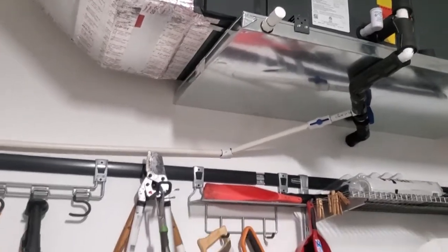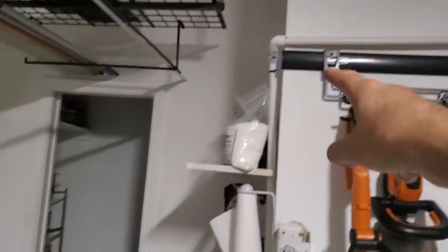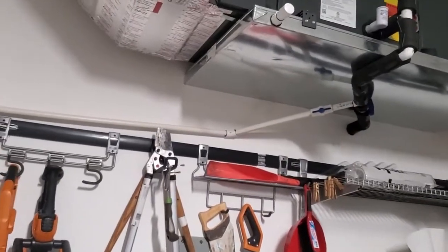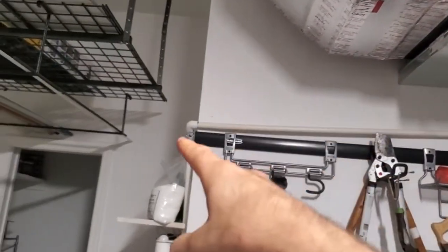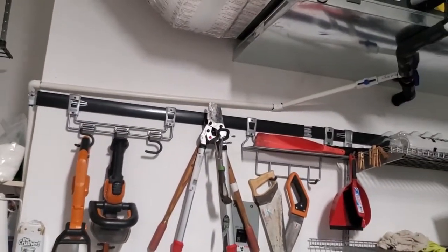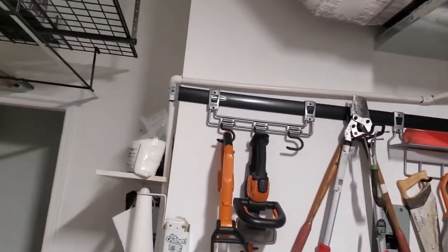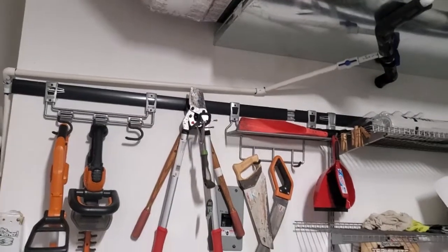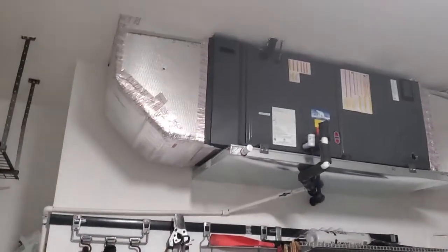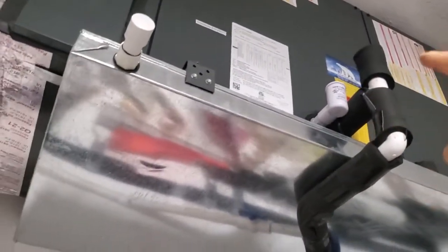Because of this continuous downward gradient, I bet this would only need to be cleaned once a year — or maybe twice, before summer and after summer, just to be safe. Even so, it's going to be a lot more reliable than the other setup, because what happened is the original line clogged up pretty quickly after the new install and kept causing system failure.